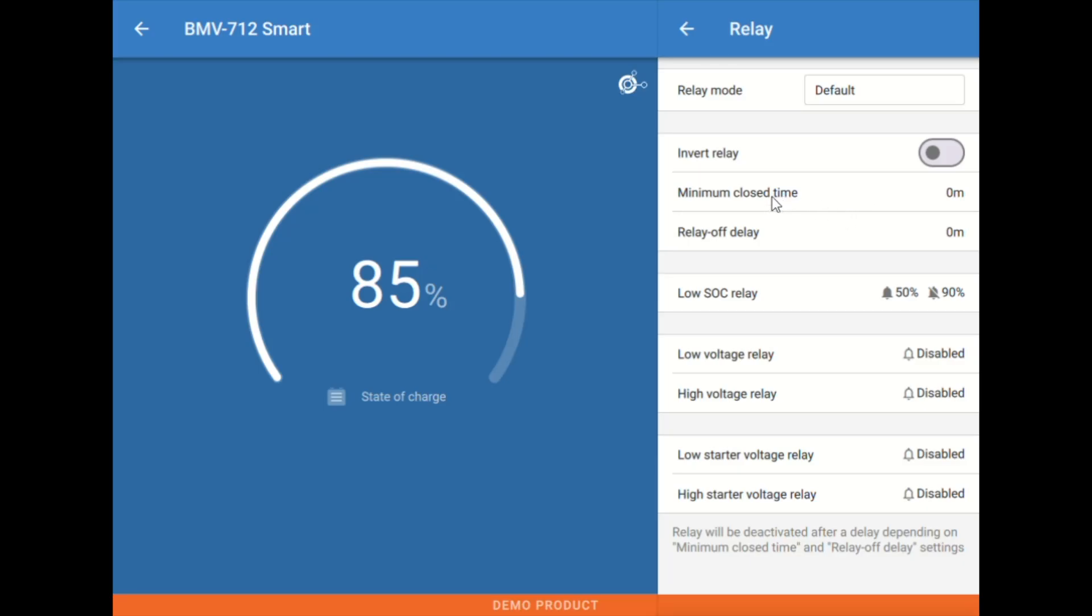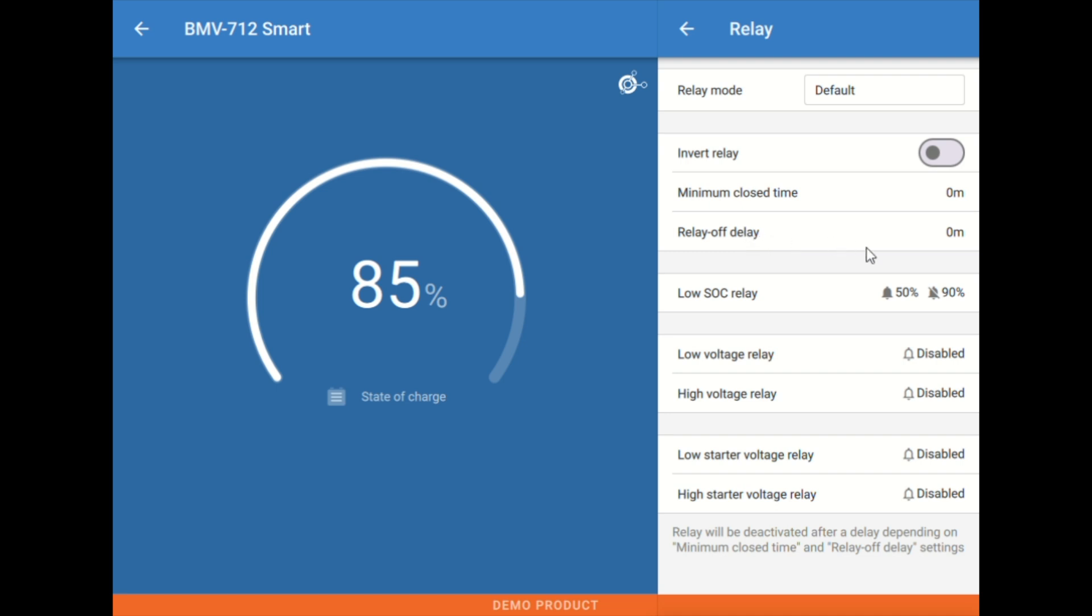We have a minimum close time, which is, if the relay is triggered, it'll have to stay closed for this minimum amount of time before it reopens, kind of like a delay where we don't, maybe in the case of a generator, don't short cycle a generator start. Same thing here, we have an off delay. So if we hit the off trigger, how long are we waiting before we actually move the relay?